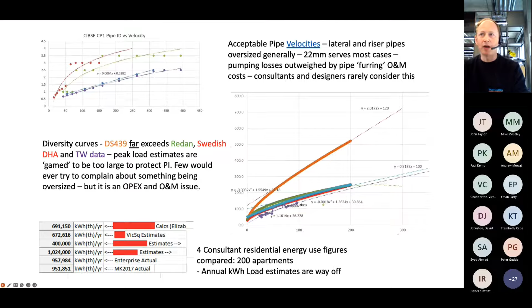So I've decided to work through just a quick one on air source heat pumps. You probably had a module previously on this one where you were talking about it. We had a new energy centre and a reputable consultant. You would recognise the name. They worked through the sizing for this new energy centre for serving a new development. We questioned their initial findings because they had storage sizing that were incorrect, boiler sizing, but mostly the addition of the diversified peak loads of the different buildings. Essentially, the Energy Pro model wasn't built right.